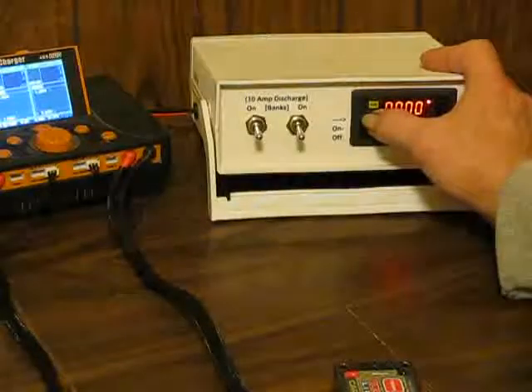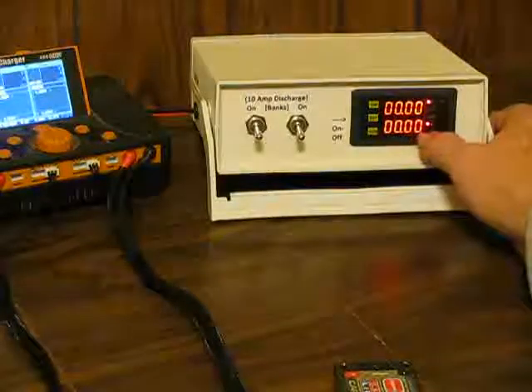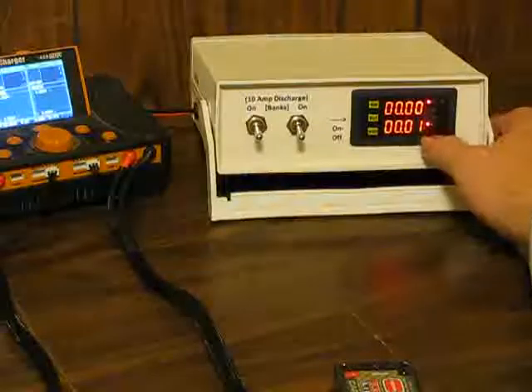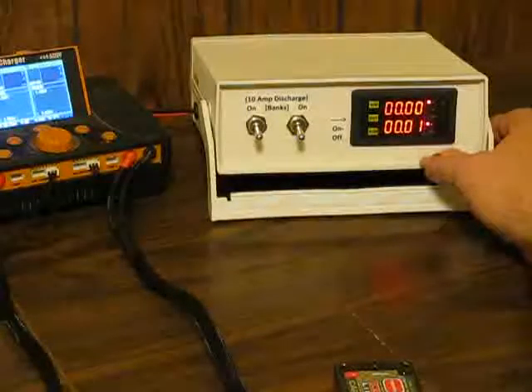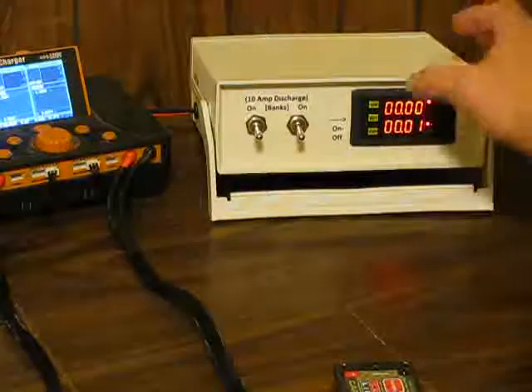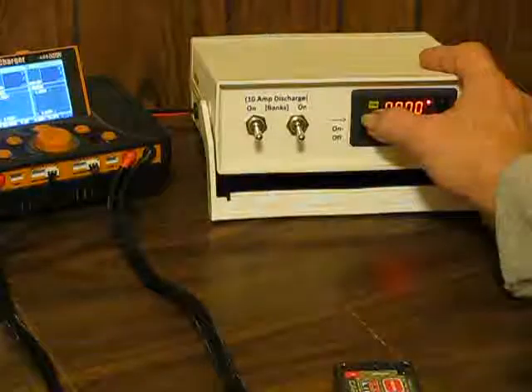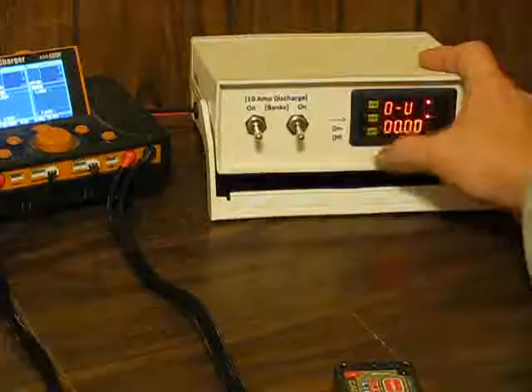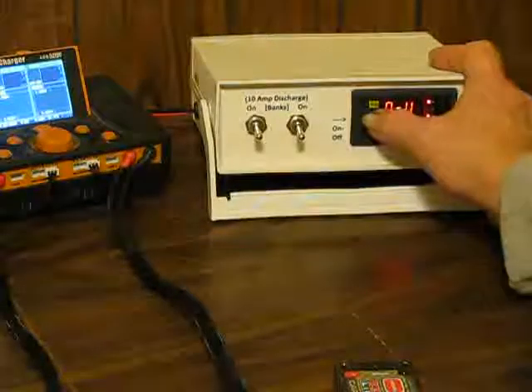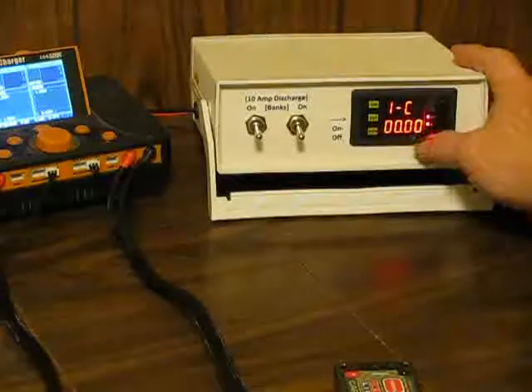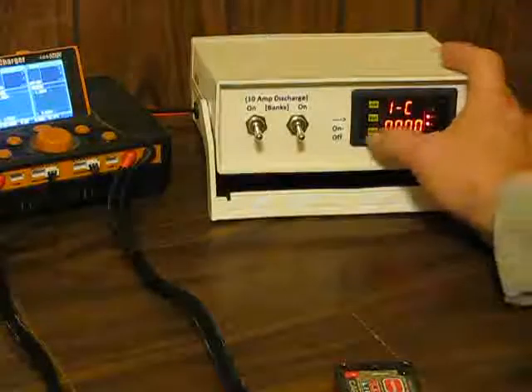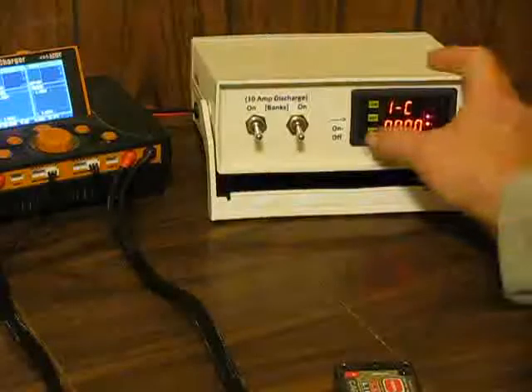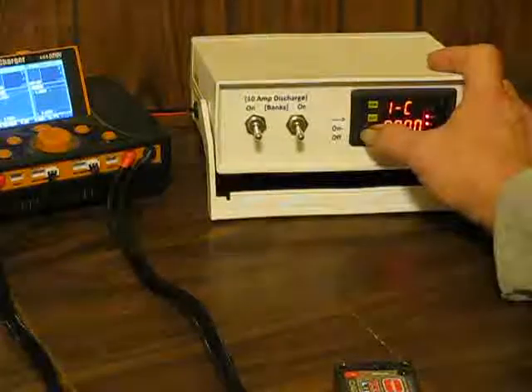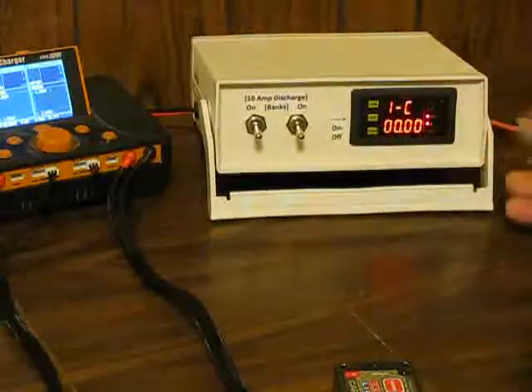Hold the button down again — looks like the amps aren't quite zeroed out, so we'll go back through and click it about 4 or 5 more times. The voltage is still holding at 0. The current shows 0, but we'll click the lower one down 4 or 5 more times — we did it 6 there.